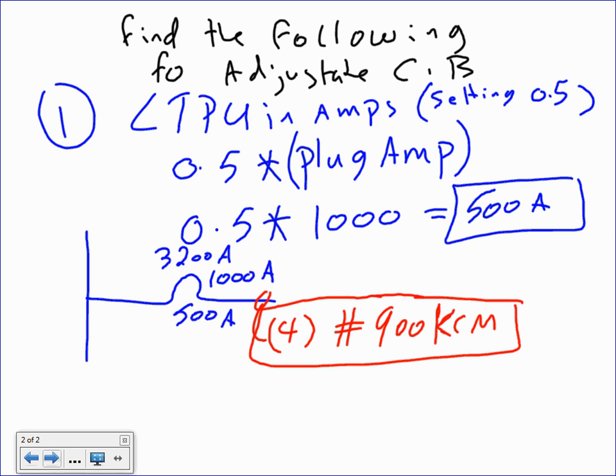But it defeats coordination. It defeats the purpose of having the adjustment to start with, because the adjustment is there to reduce the number of conductors. But you could reduce it down with the circuit breaker. I know, but I'm just saying, if you know that in 5 years it's going to be larger.